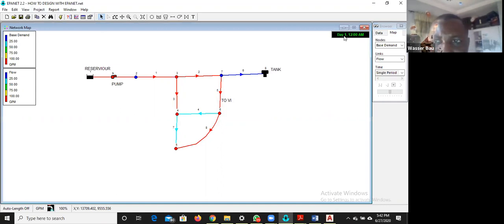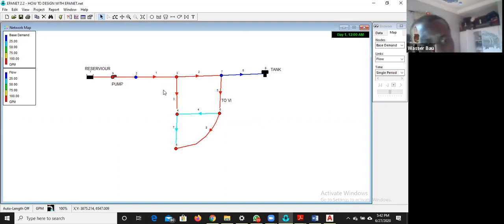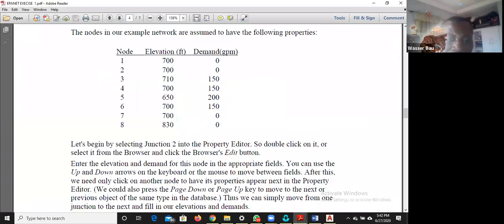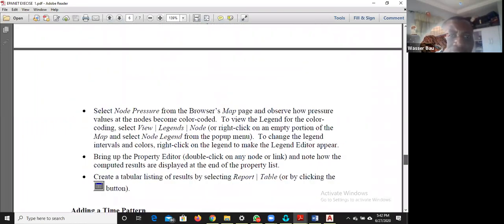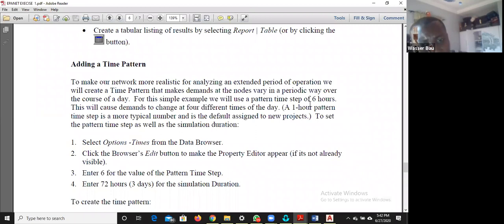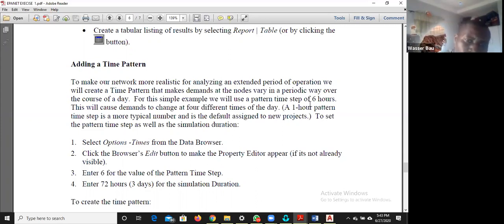Now we will run a simulated extended-period analysis using a time pattern. A time pattern shows the variation of water demand throughout a day. Typically there are four time periods in a day: midnight to 6 a.m., 6 a.m. to noon, noon to 6 p.m., and 6 p.m. to midnight. Morning hours are peak periods — as a designer you must account for these peak demands.